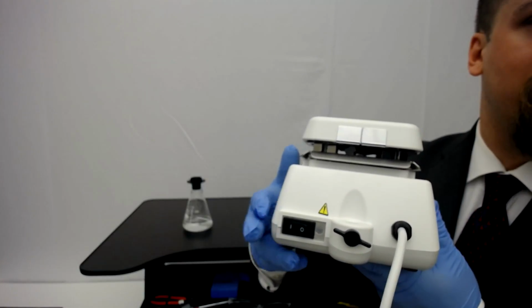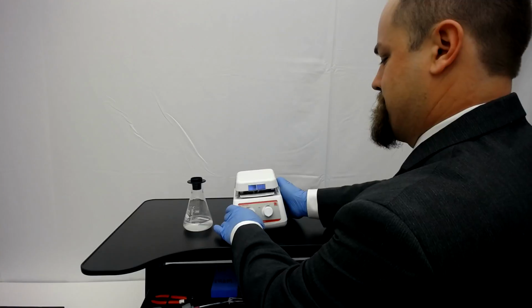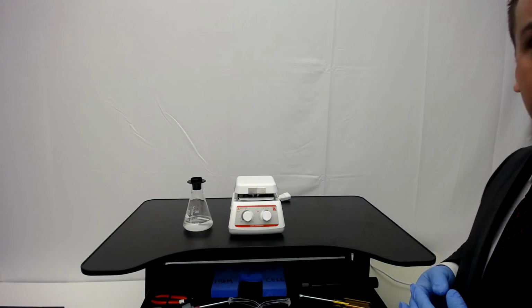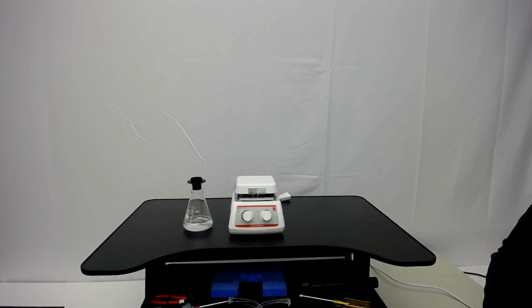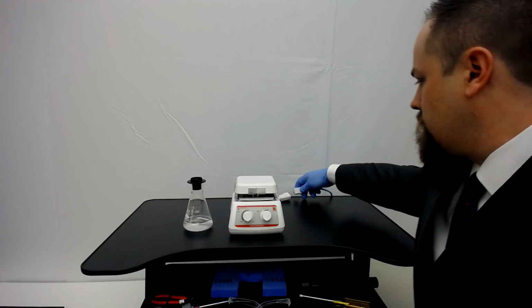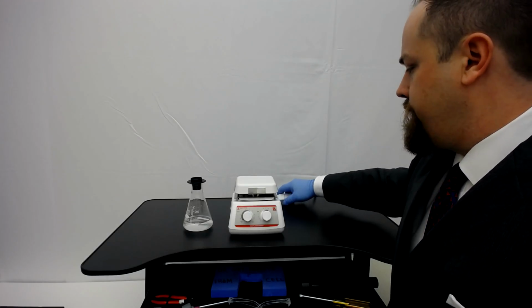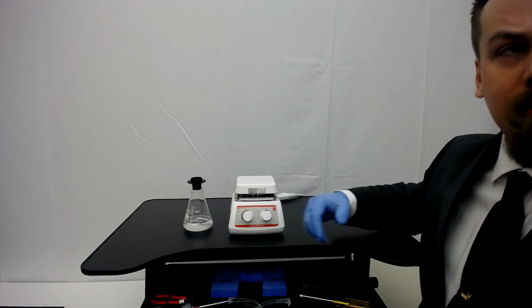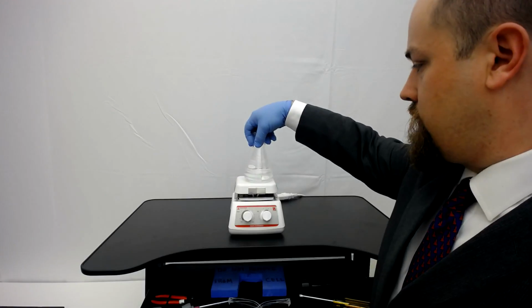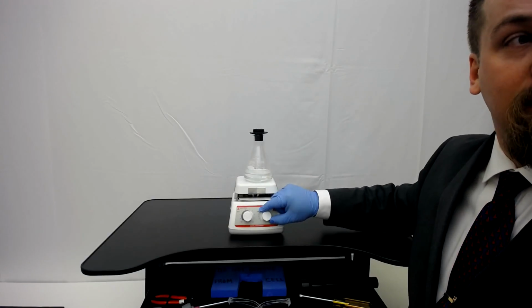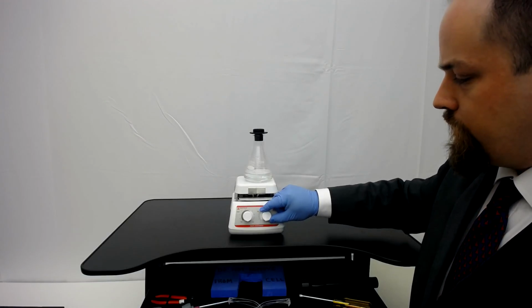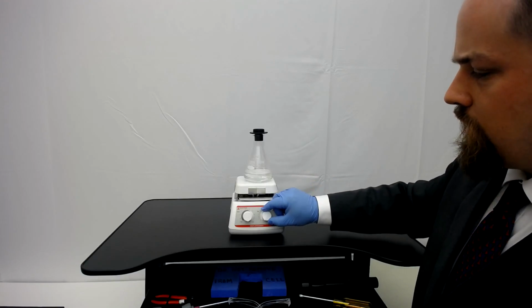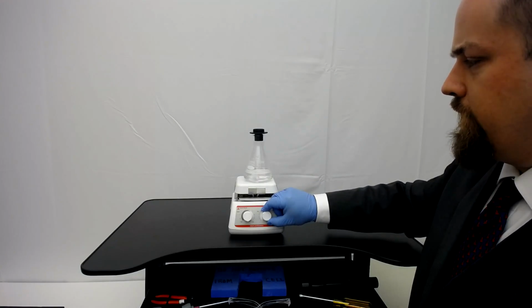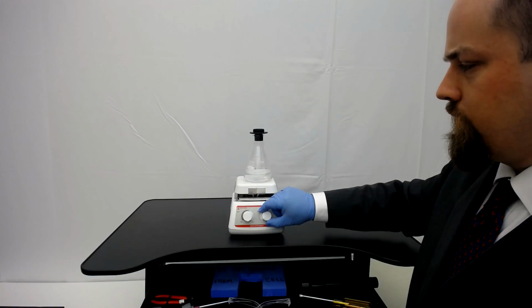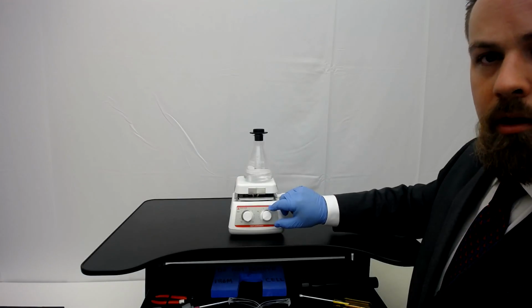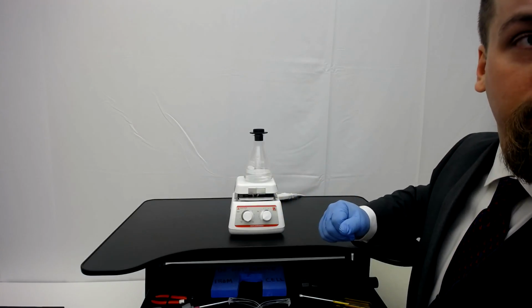Stirring units don't necessarily have this hard on-off, but it's there for safety for the heating units. As you turn this up, if you set it to a very low speed, sometimes it needs to overcome friction. So I'll set this on here to let you see it. Sometimes it needs to overcome motor friction before turning on. So if you set it to 1, sometimes it doesn't start right away until you turn it up a little bit, get it started, and then you can move it down to the desired speed. This unit right now is not calibrated, so we will be going through that calibration for you.